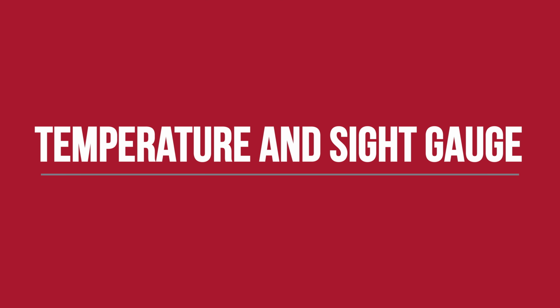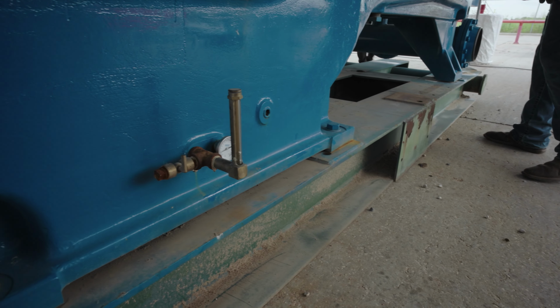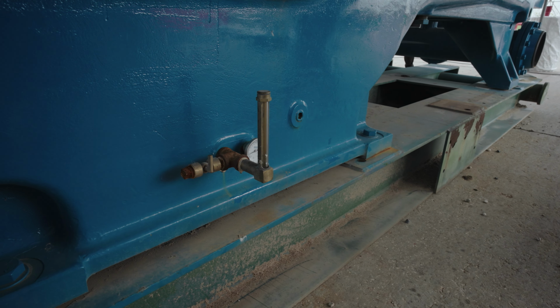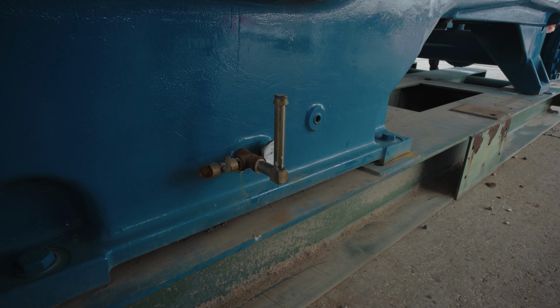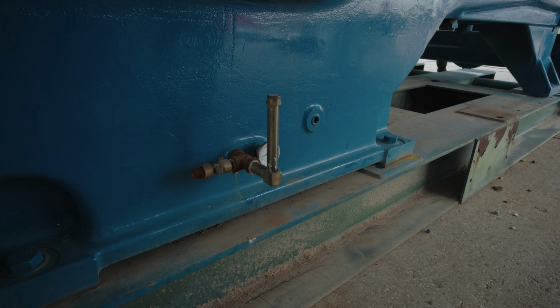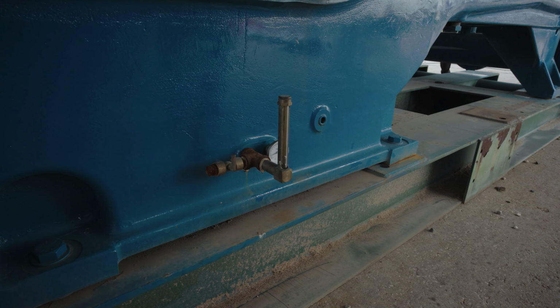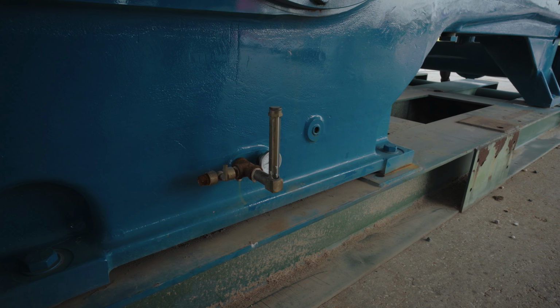Next, check the temperature gauge for your oil temperature and your sight gauge for oil level. When full and idle, the oil level will be about 1/4 of an inch from the top or about the 3/4 level in the window. When the pump is in operation, the oil level will settle to the half full range. Temperature range will vary depending on operating conditions. Higher operating temperatures above 150 degrees should be noted and the oil plate chart on the side of the pump consulted.